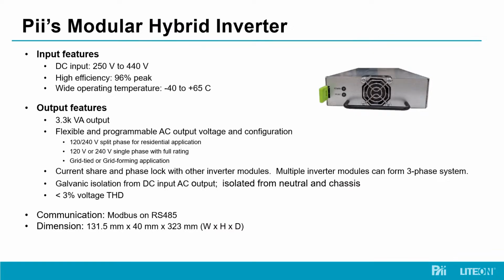Now, if you're using 480 applications, by stringing three of those modules into a shelf, it can also provide 277 volt output to create a three-phase output that matches the 480 volt Y of the rectifier.